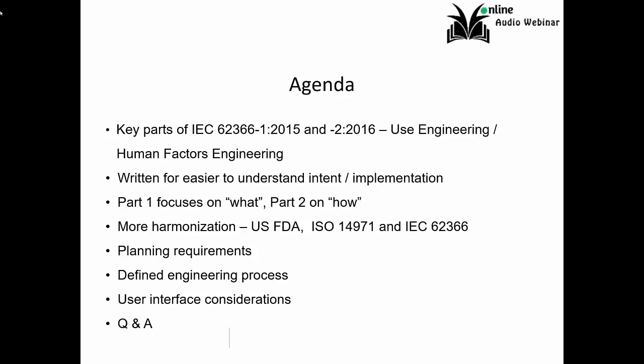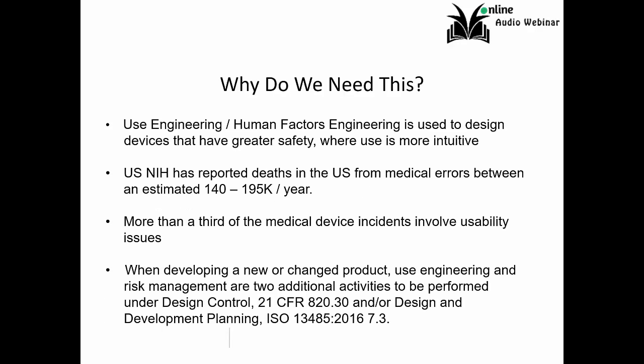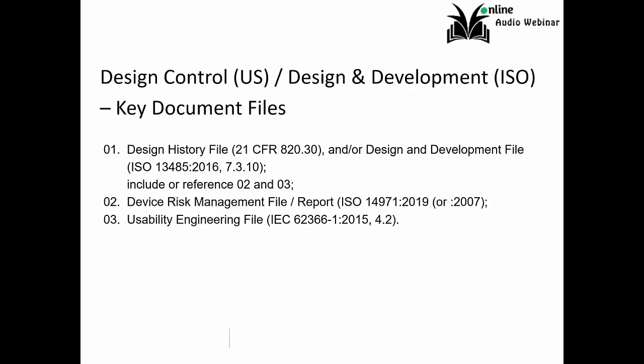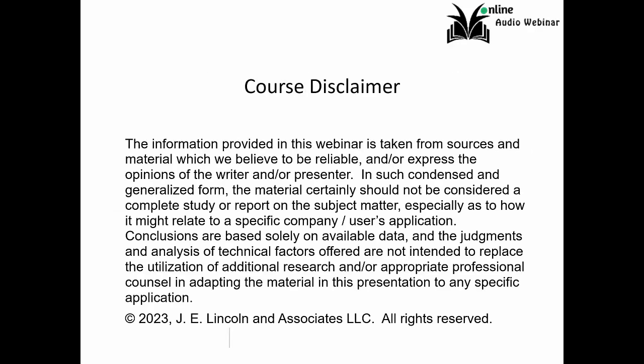IEC 62366-1 is only used where the interface is not familiar to your user, or there could be misunderstandings with the interface. So you want to test it and try to drive the use of the interface down to its most common level. It's where it's intuitive, if you will. Same thing for risk management. The same issues drive the demand for use engineering. And once again, the key document file is the design history file, the top level file, risk management file mandated 100%, and use engineering as needed. Supplemental files to the design history file. So that concludes the fifth of our 6 modules.